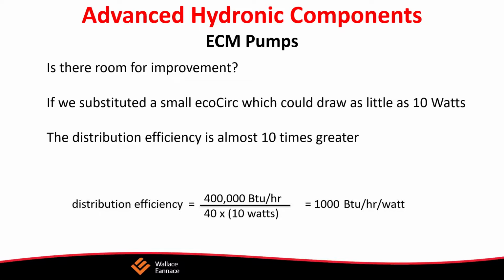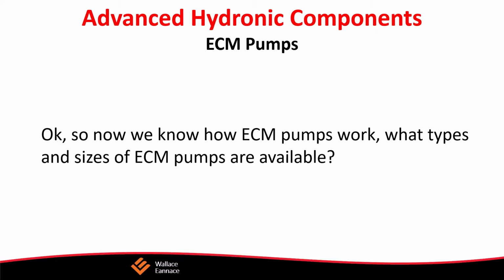So when we talk about ECM pumps, and about efficiency in general, really that is the desired output divided by the necessary input. One of the things that we talk about here is the distribution efficiency for a space heating system. The distribution efficiency is the rate of heat delivery divided by the rate of energy used by the distribution equipment. So if we have a system that delivers 120,000 BTUs at a design load condition using 4 circulators at 85 watts each, the distribution efficiency of that is 120,000 BTUs divided by 340 watts, which would equal 353 BTU per hour per watt. Well, what does that mean?